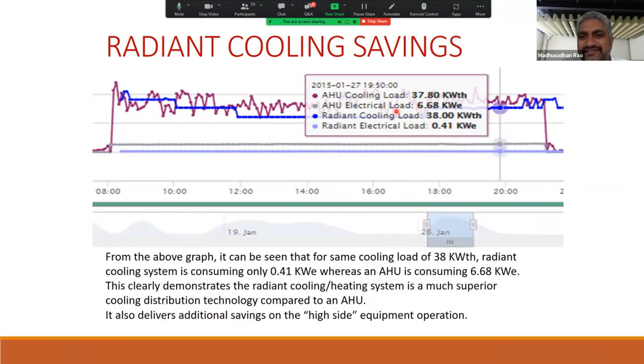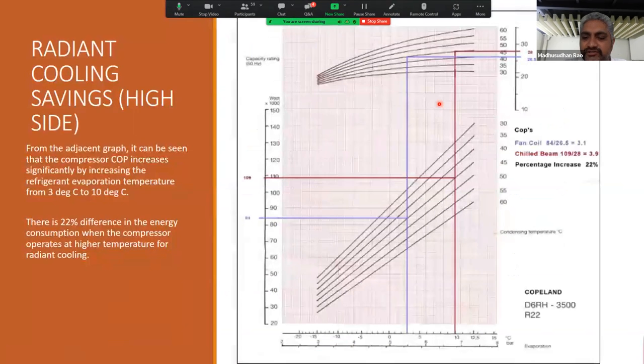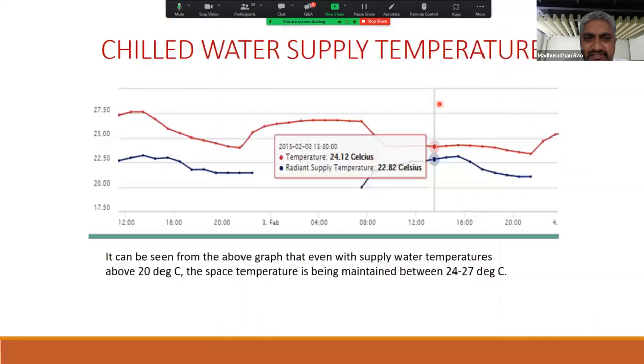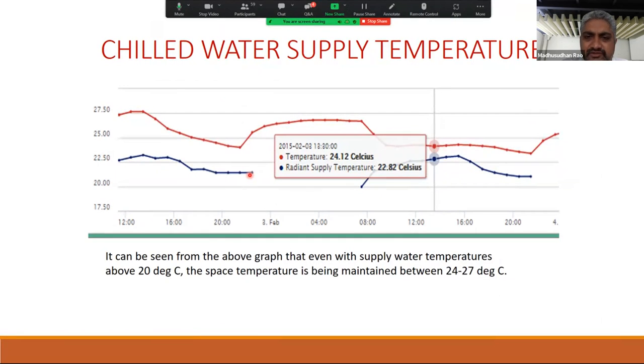Okay. But it's not just restricted to the low side. It also brings benefit on the high side, because if you see the temperatures that are required, as I mentioned, in this particular case, we have used slightly higher temperatures, but usually you could say about 15 to 16 degrees centigrade. This is the space temperature that is being maintained. In this case, it's being maintained at, on an average, let's say 26, for which the supply temperature was more around 20 or 21. Okay. So to maintain 24, usually we suggest about 16 degrees centigrade.